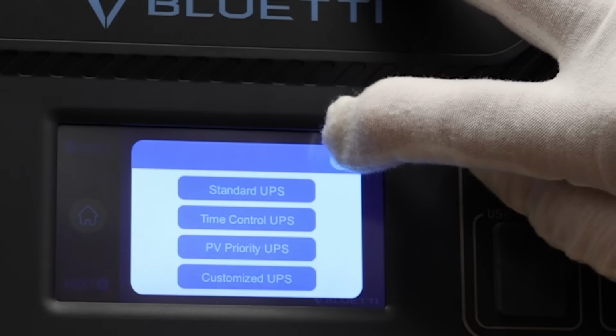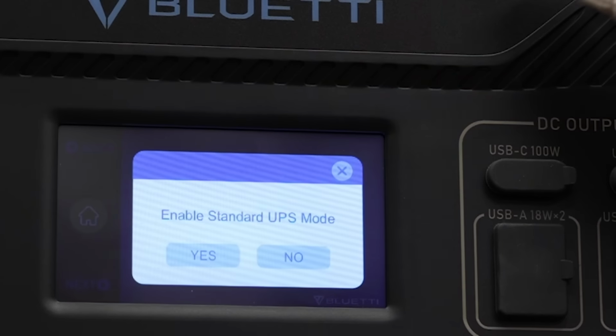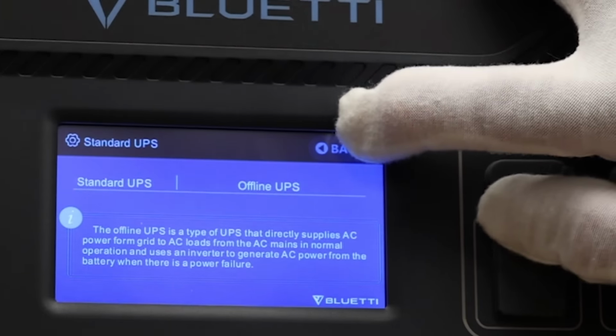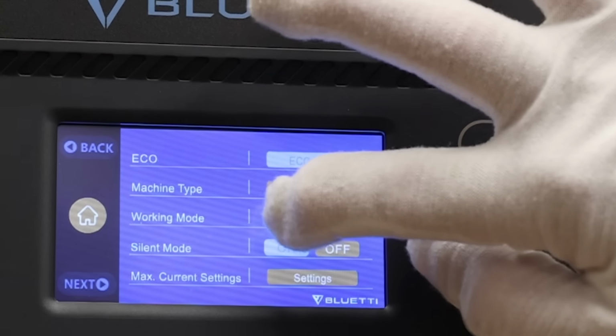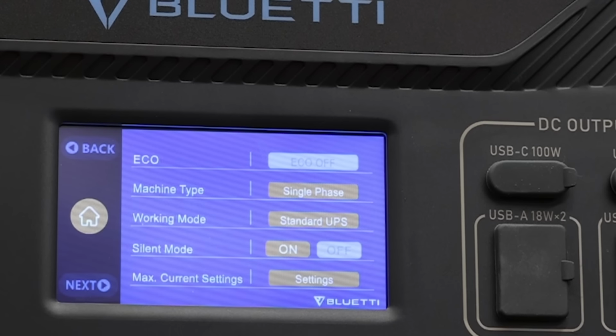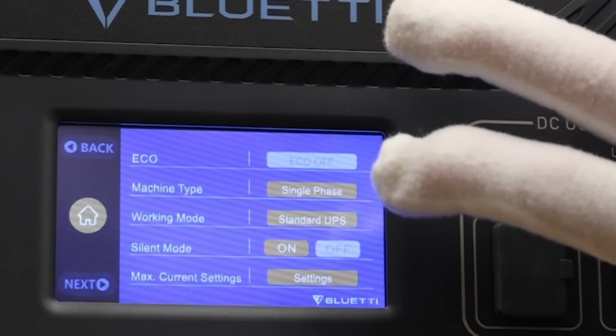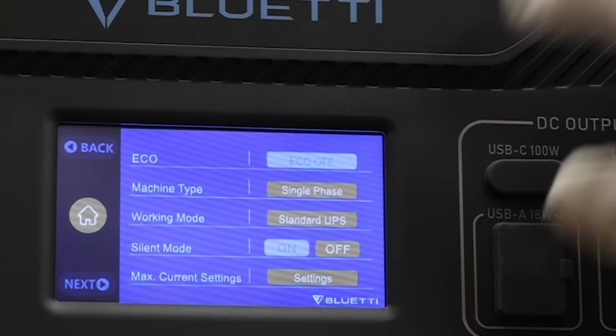UPS: there are 4 different UPS systems on this, I'm not going to go through it here — almost everybody leaves it on standard UPS. Silent mode, on or off: if you turn it on, it runs the fans at a quieter speed, but also limits your input and output, so I leave that off. We just saw what the max current setting does.